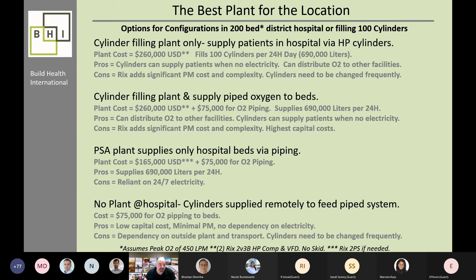We are finding that we can do oxygen piping safely at much lower costs than in the global north. And these costs range really between as low as $300 to $500 or $600 per bed in hospitals. So it's really something that should be considered more often because this can really simplify your plant. Next slide, please.